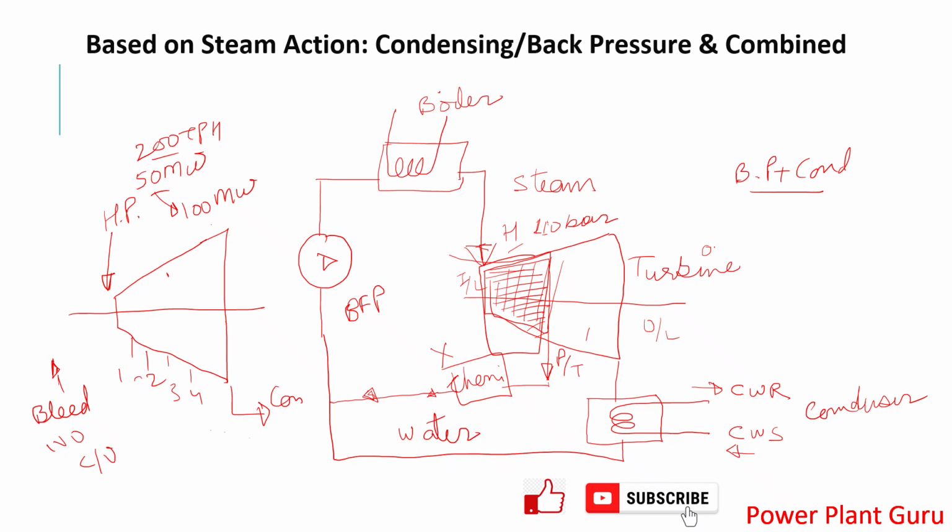It will change based on the total steam flow. This kind of setup is normally used in an independent power plant where you will have a lot of HP heaters, a deaerator, and LP heaters as well, which use the steam drawn from the turbine for feed water heating.